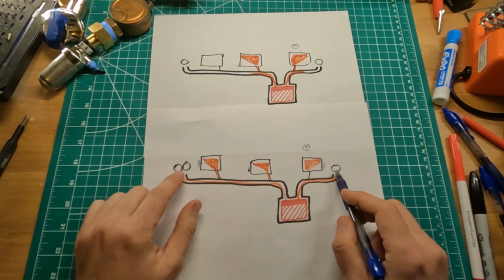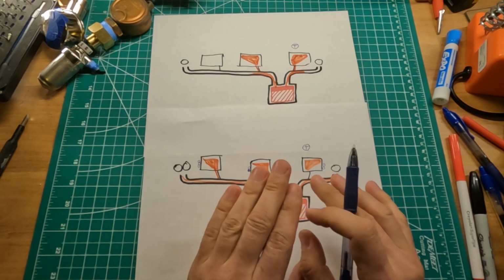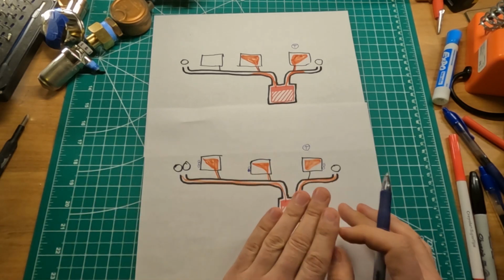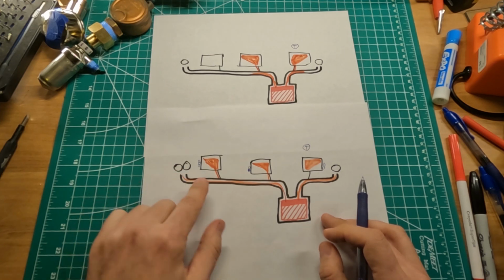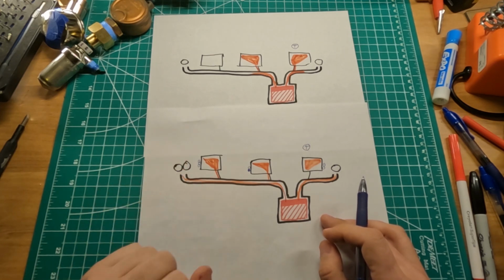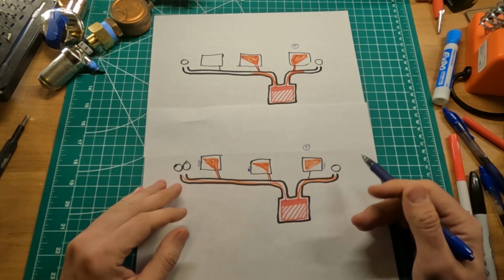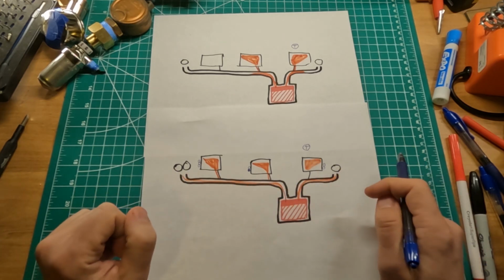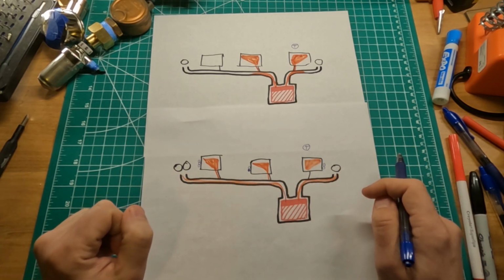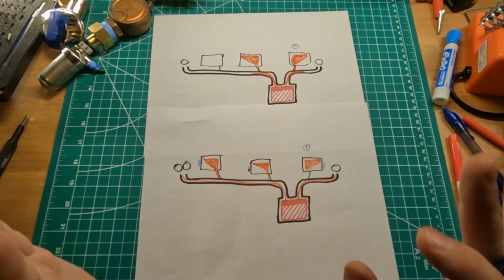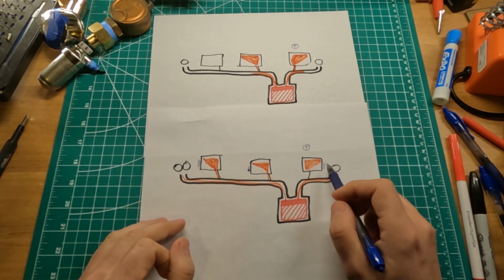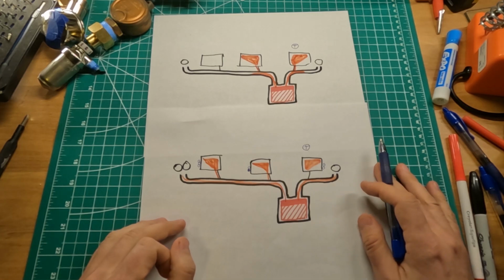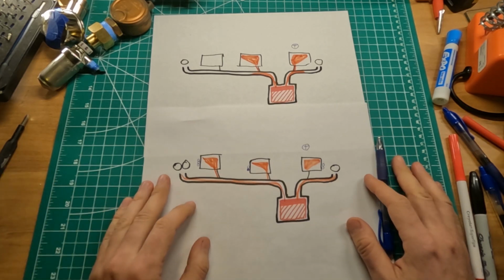So because of that, main venting is very important, because then that little bit of steam just always wants to go on the path of least resistance, which is the main, where there's the highest amount of venting. So again, as always, vent your mains as quickly as you can, and then your radiators, try to slow them down so that you don't get too much condensate spitting out of your air vents. That's it. I hope that was helpful for somebody.